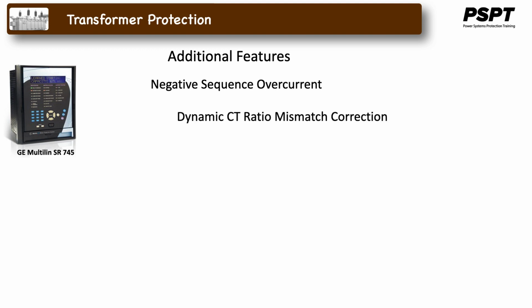Dynamic CT ratio mismatch correction accounts for variations in on-load tap changer positions. Tap positions are monitored and CT ratios are corrected accordingly, automatically.